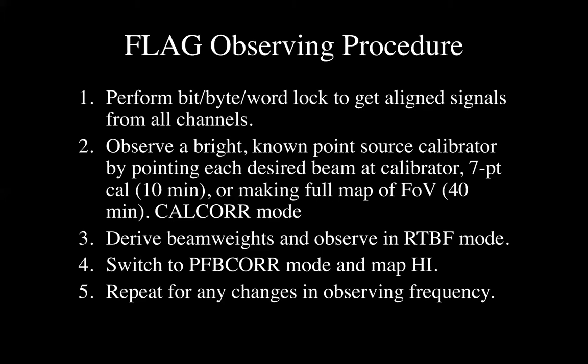That's just doing a series of RA long maps, say, in this CALCORR mode, with regular position, off-source reference positions for calibration purposes. When you do a full map, you get a full map of the sensitivity of the telescope, which I'll show you in a bit, and full beam maps as well. But you can also place your beams wherever you would like within that field of view then. Wherever you've collected data as you're scanning the telescope, you can place the beam. So you have a lot of flexibility there, for better or worse.